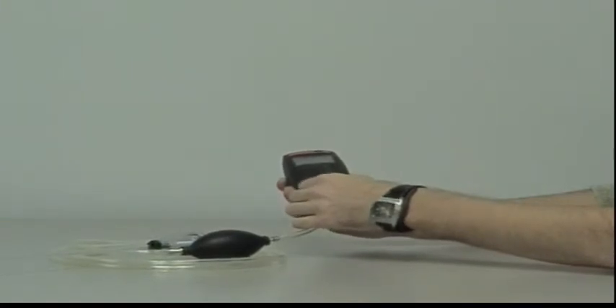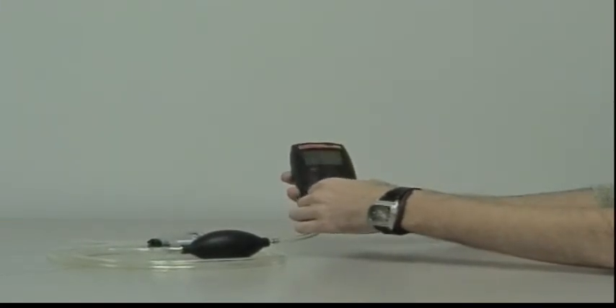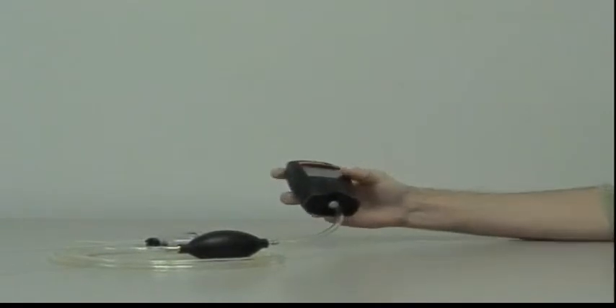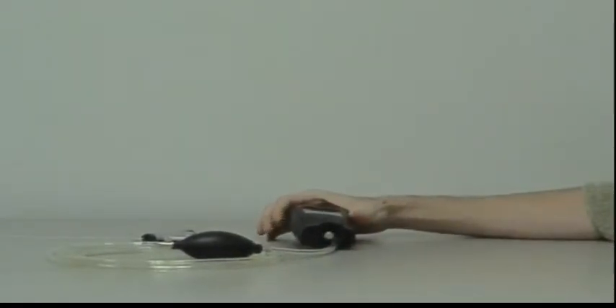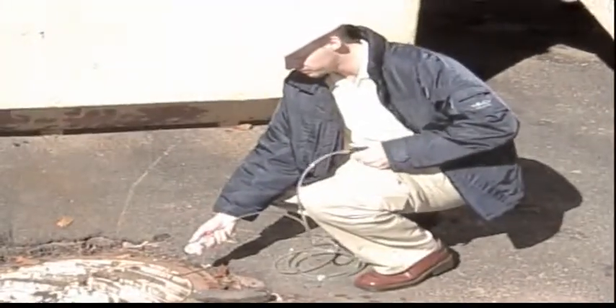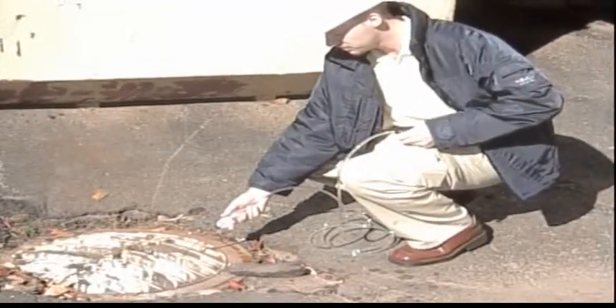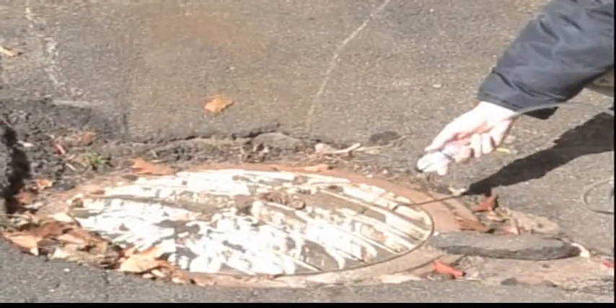Secure the calibration adapter to the MultiPro by inserting the tab and tightening the knurled screw at the top of the adapter. Insert the end of the sample draw probe into the location to be sampled. Squeeze the aspirator bulb several times to draw the sample into the sensor compartment.